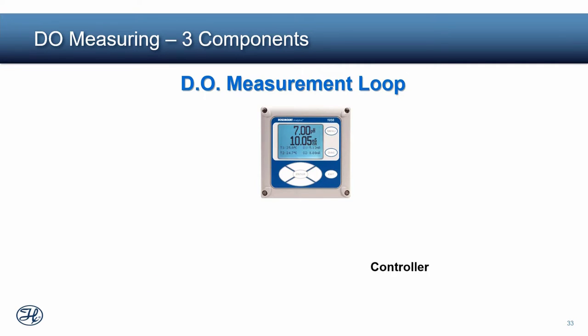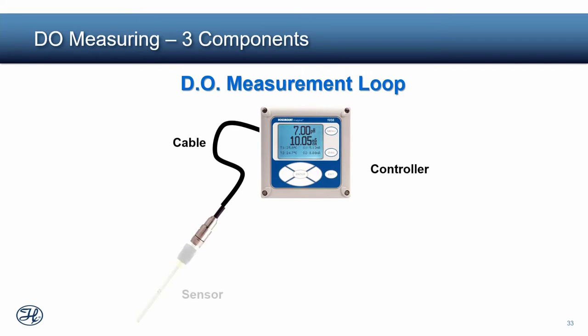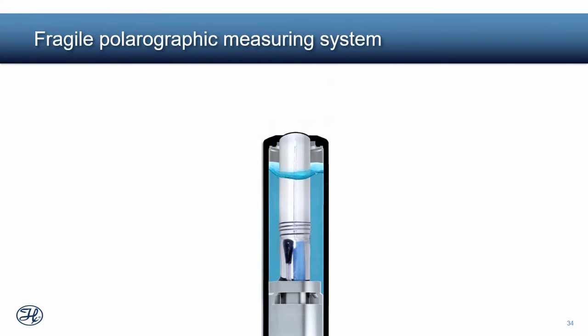And that gives you a measuring loop. Okay. So you have a controller and a cable, and that goes to your sensor. And this gives you a nanoamp loop, and you have to calibrate all of this, including the cable and the controller, to your bioprocess or to your bioreactor, because every controller has different impedance, every cable has a different impedance, and your sensor is different because of all the components. It's actually a very fragile measuring system.